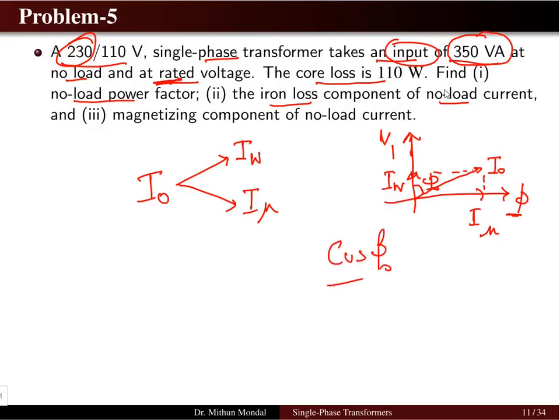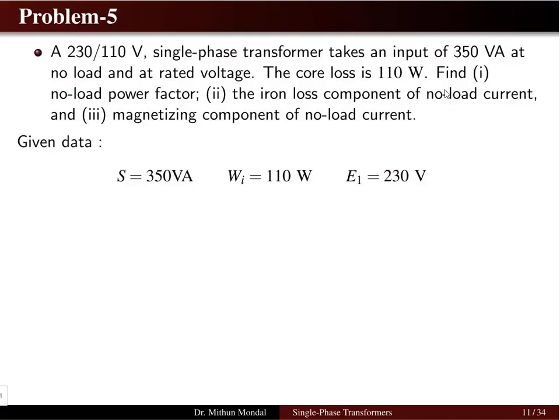So here the iron loss component is basically the IW component and the magnetizing component is basically the I mu component. The data given is the apparent power or the kVA rating of the transformer under the no load condition, the iron loss or the input power, and the induced EMF on the primary side.